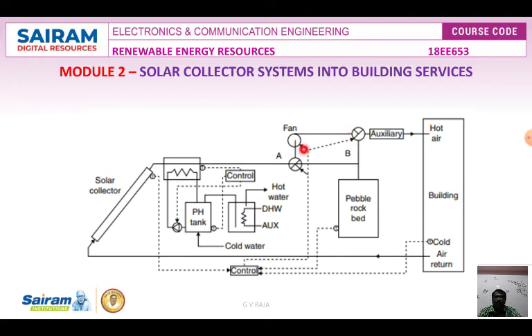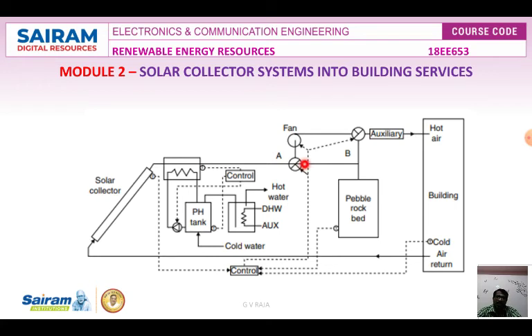In the first mode — when both dampers A and B are open — this is the normal daytime solar heating mode. The storage unit is bypassed. If the temperature sensor on top of the collector array reads below the level required for space heating, the auxiliary furnace automatically turns on and stores the thermal energy in the storage tank.